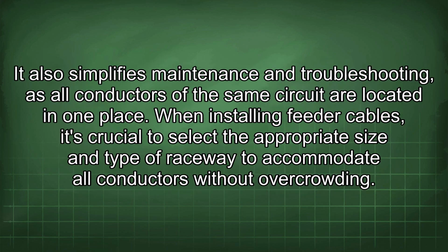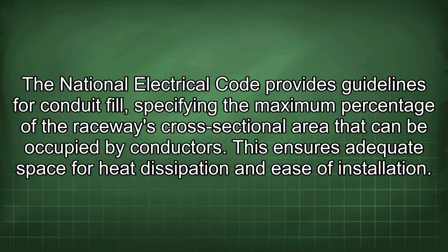It also simplifies maintenance and troubleshooting, as all conductors of the same circuit are located in one place. When installing feeder cables, it's crucial to select the appropriate size and type of raceway to accommodate all conductors without overcrowding. The National Electrical Code provides guidelines for conduit fill, specifying the maximum percentage of the raceway's cross-sectional area that can be occupied by conductors. This ensures adequate space for heat dissipation and ease of installation.